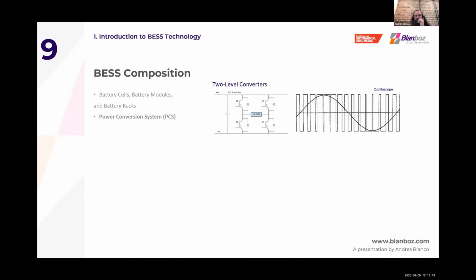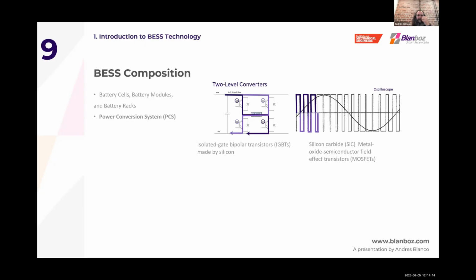The most common type you'll see between central and string inverters is the two-level converter. There you have filters and transistors that essentially flatten the DC current, opening and closing very fast to change the flat signal into a sinusoidal curve. If you put an oscilloscope there, with the two bridges interacting, you'd see the upper bed, then the reverse current opening and closing again giving you the bottom bed. Over time, you get an almost perfect, or even perfect, sinusoidal curve. That's what you need for AC to synchronize with whatever equipment you have, or with the grid.